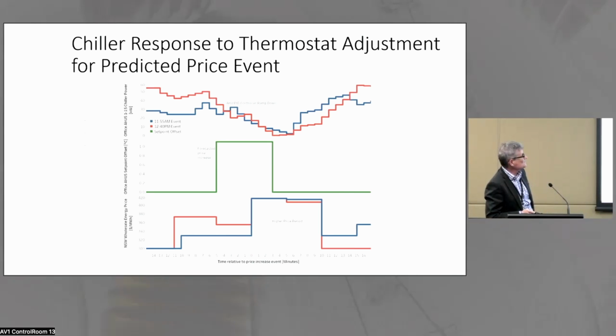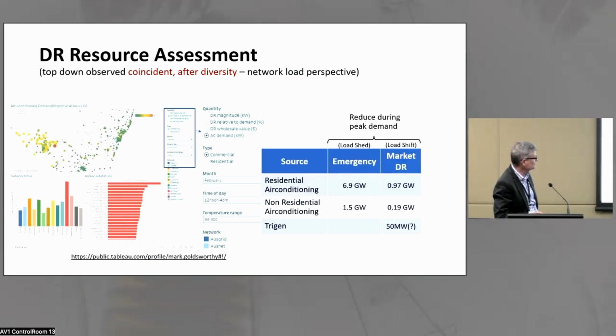This one is a chiller response to a thermostat adjustment. At the bottom of the plot is the forecast of the price in the NEM, and then the signal to switch the thermostat. You see the result in two different trials, the blue and the orange, showing the response of the chiller or air handling unit to the thermostat adjustment. What you see is that the actual dynamics here is not the building thermal physics — at this time frame, it's actually more based on the equipment plant itself and the PID loop around the controller. So there's a fair bit of nuance we'll be teasing out in these flexible demand strategies. It's not just a straight down, flat, straight back up profile.